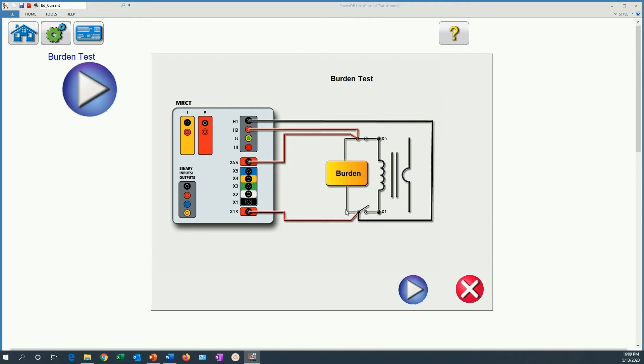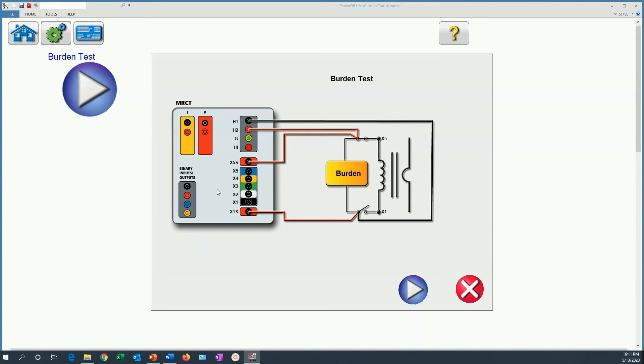Remember to take the CT out of the equation. It is very important that when you are doing a burden test, the CT is not part of the circuit under test. So you disconnect the CT and you connect only to the CT's load. When you are doing a burden test, you will be injecting a single phase current through the circuit of the relays connected to the secondary of that CT.